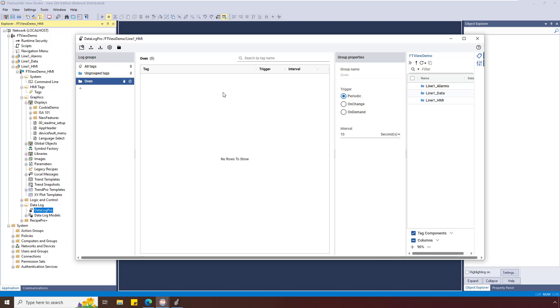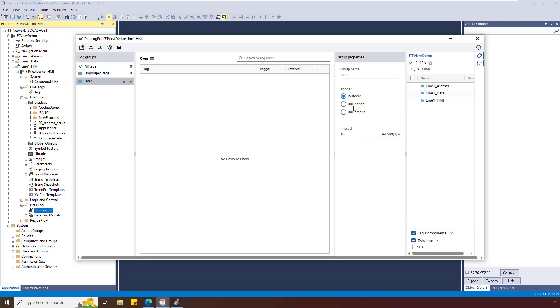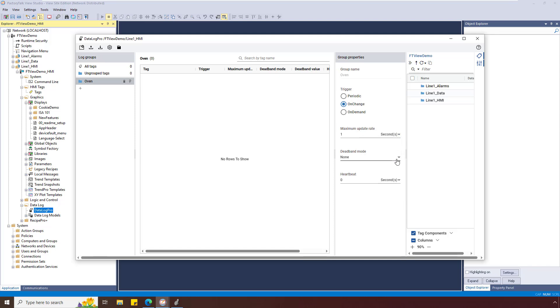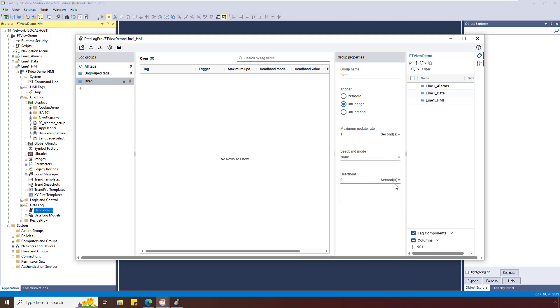Once a group has been added, you can configure how the group is triggered in the Group Properties pane. Periodic includes intervals from milliseconds to days. OnChange has maximum update ranges of milliseconds to hours, and supports a deadband mode of percentage or absolute values, and a heartbeat range of seconds to days.